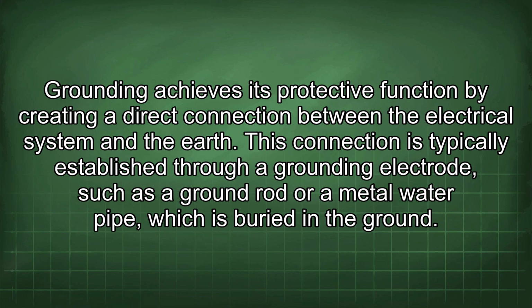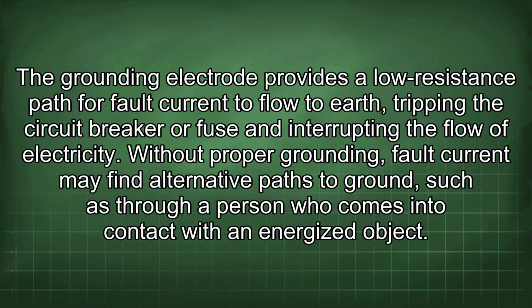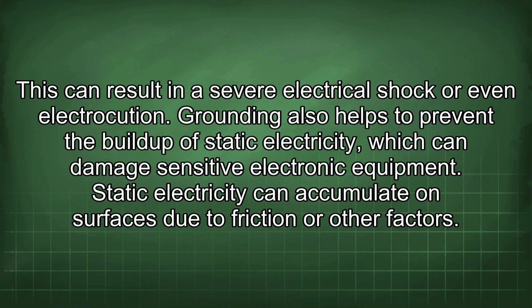Grounding achieves its protective function by creating a direct connection between the electrical system and the earth. This connection is typically established through a grounding electrode, such as a ground rod or a metal water pipe, which is buried in the ground. The grounding electrode provides a low resistance path for fault current to flow to earth, tripping the circuit breaker or fuse and interrupting the flow of electricity. Without proper grounding, fault current may find alternative paths to ground, such as through a person who comes into contact with an energized object. This can result in a severe electrical shock or even electrocution.